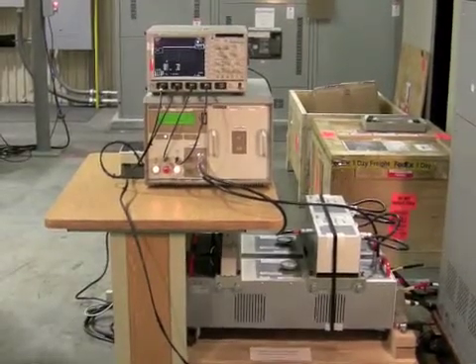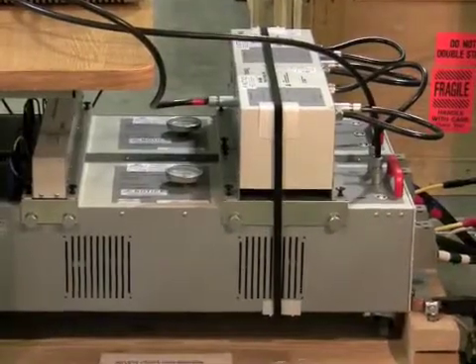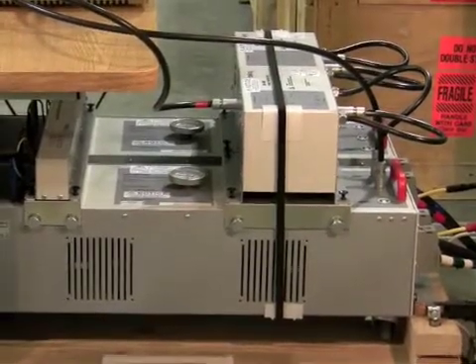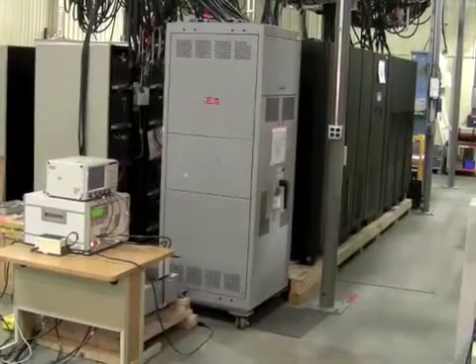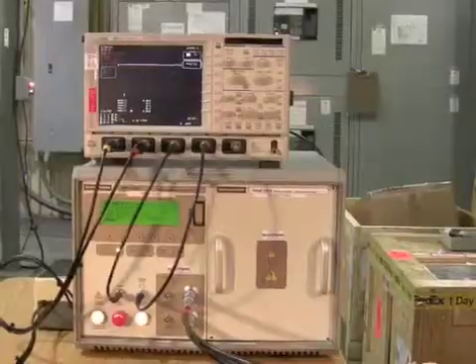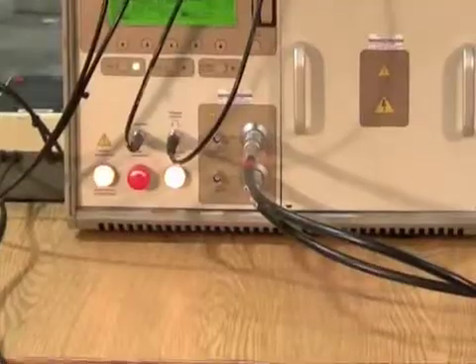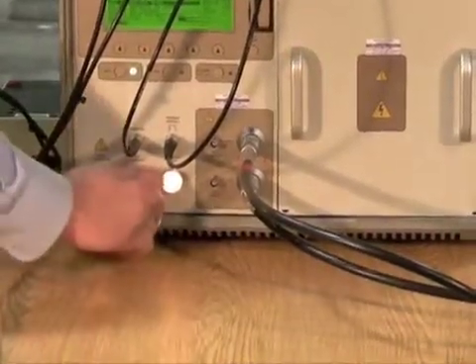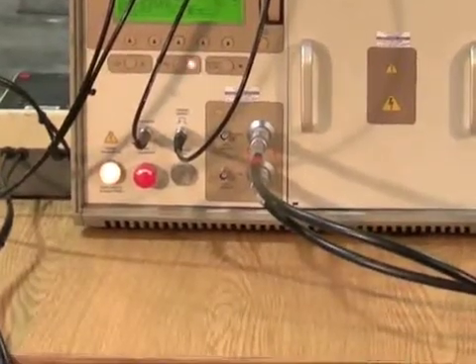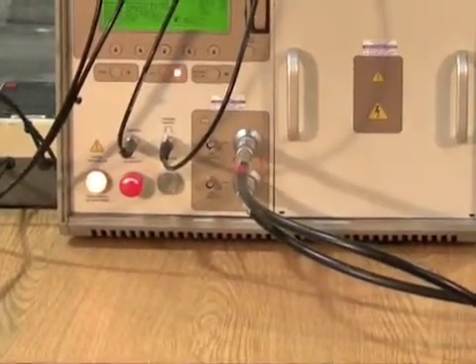Here we have the Keytek surge generator machine that we're going to use to test our 1100 kVA 93-95 UPS for input surges. Underneath the Keytek machine we see the coupling network, which physically couples the surge onto the input voltage bus bars of the UPS. On the right-hand side of the screen we can see the 1100 kVA UPS running at 100% load. We've placed an oscilloscope on top of the Keytek machine so we can see the surge and the resultant output in real time. The test begins — each time the red LED lights, a surge is being applied to the input of the UPS, so we are seeing multiple repeated surges during the course of this test.